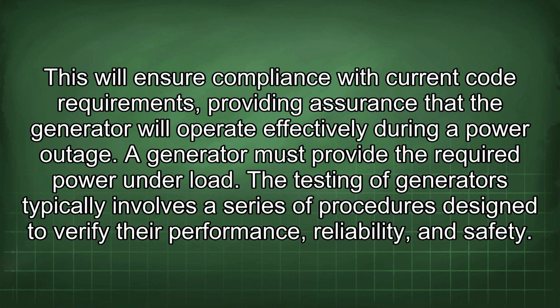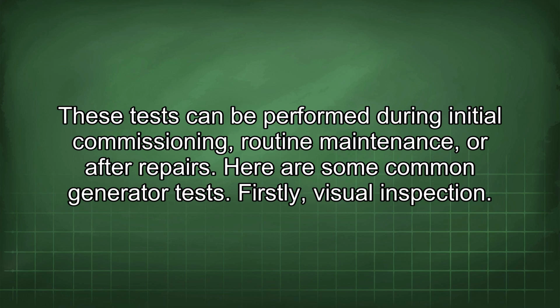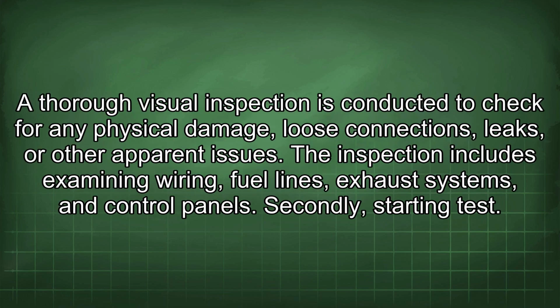A generator must provide the required power under a load. The testing of generators typically involves a series of procedures designed to verify their performance, reliability, and safety. These tests can be performed during initial commissioning, routine maintenance, or after repairs. Here are some common generator tests. Firstly, visual inspection. A thorough visual inspection is conducted to check for any physical damage, loose connections, leaks, or other apparent issues. The inspection includes examining wiring, fuel lines, exhaust systems, and control panels.